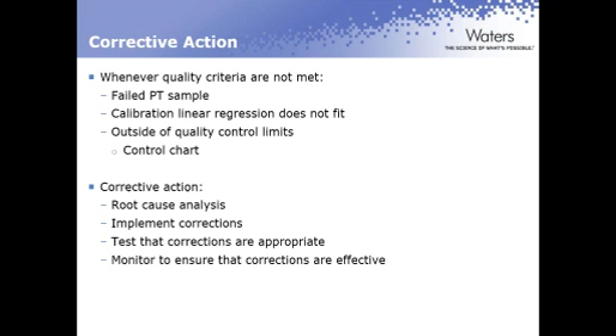And then we need to make sure that we monitor that those corrections are effective. We want to make sure that running the CRM once, we didn't just get lucky. We want to monitor it as we continue to run that CRM or as we continue to run PTs, to make sure that the corrections we made are effective. Okay. CRMs are incredibly effective when conducting those root cause analyses. You want to make sure in doing a root cause that you're running stuff using the same conditions that you did when the problem was identified. Make those minor adjustments. Use your CRMs to identify the source of the error.